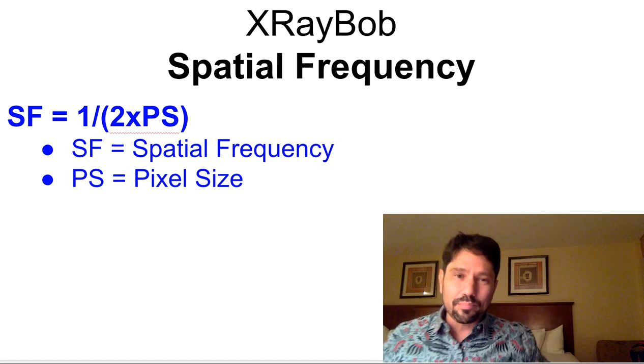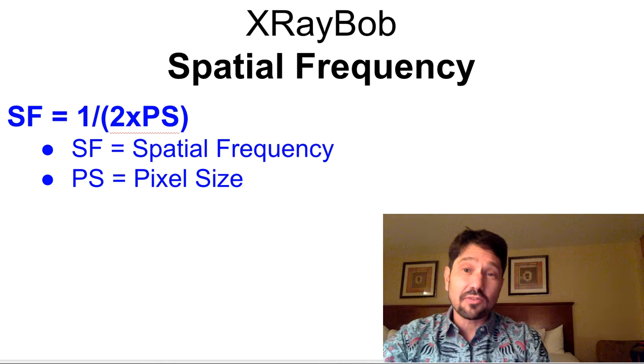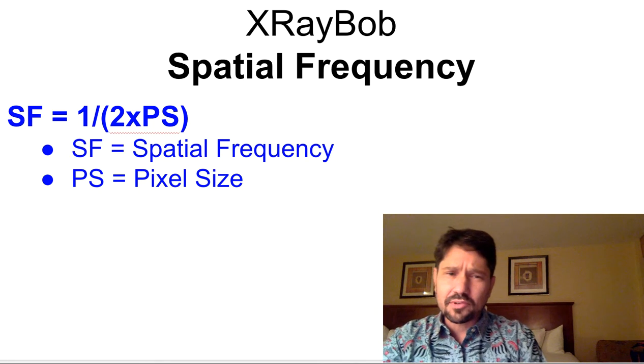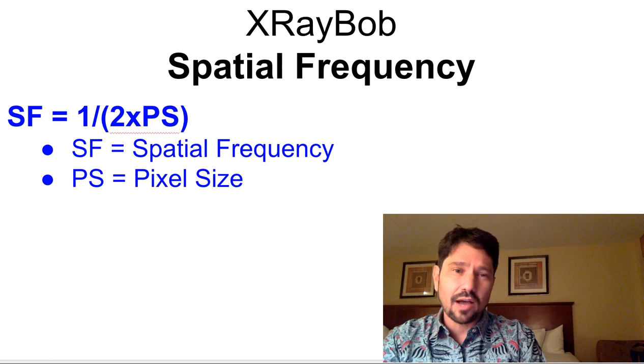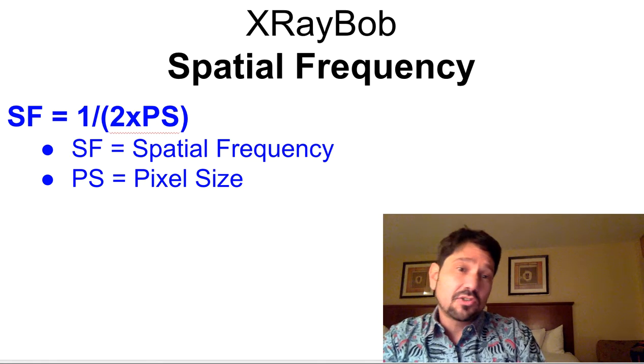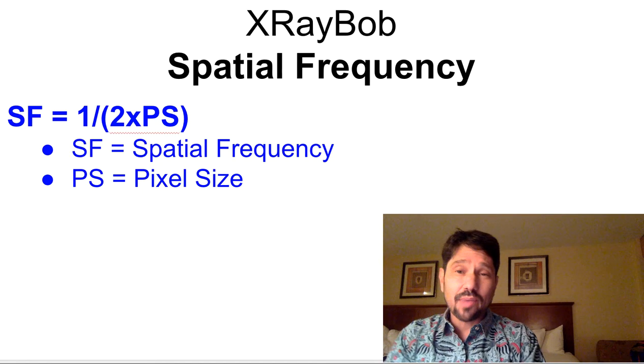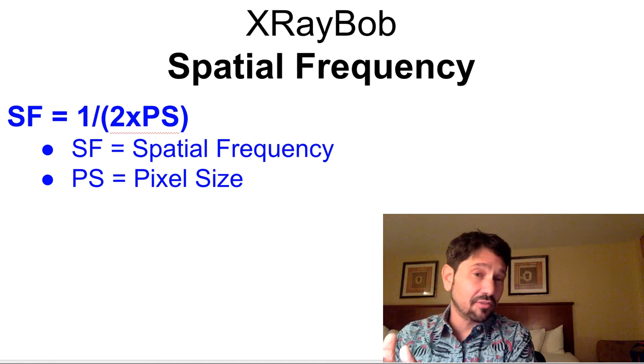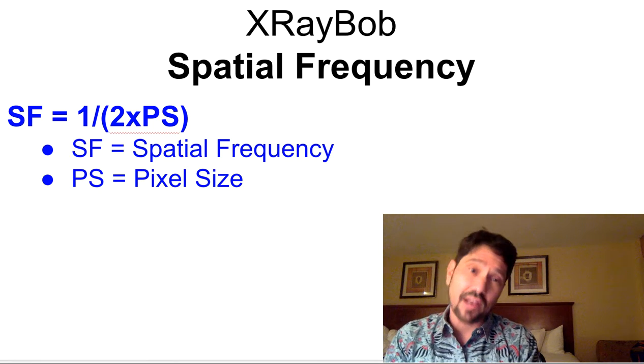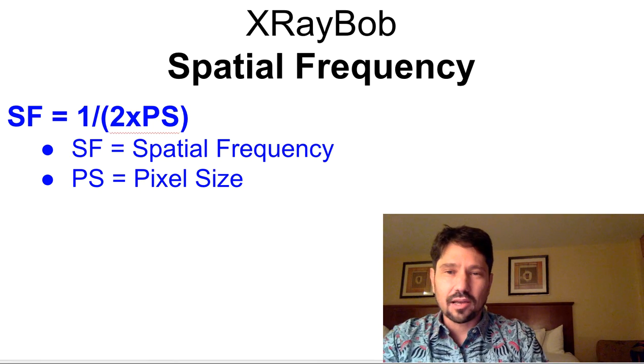All right, so the formulas you need to know. The first one you need to know is spatial frequency, SF, sometimes referred to as spatial resolution, equals 1 divided by 2 times the pixel size. And it's 2 times the pixel size because spatial frequency is expressed in line pairs. So there's a pixel for the line and a pixel for the not line. So that's how we get to line pairs.